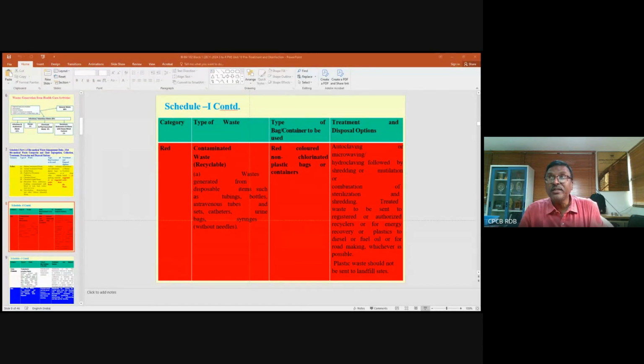Therefore, when you are adopting the autoclave, it should operate at 121 degrees centigrade, 15 psi pressure, and not less than 60 minutes. That is the duration you have to adopt. Secondly, the disinfection efficiency depends upon the quality of chemical used. If you are using a chemical disinfectant and adequate residual chlorine is not available, then you cannot achieve the desired efficacy. If the hypochlorite solution does not have the suggested percentage, then also you will not achieve the desired efficacy. Therefore, the disinfection efficiency depends on the quality and quantity of chemicals used for treatment of biological waste, and also contact duration.